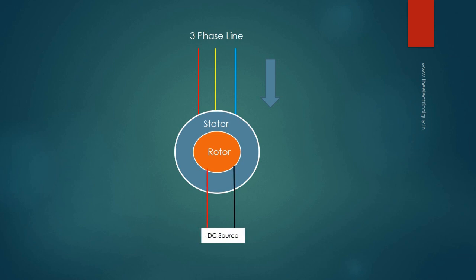If we excite the rotor with DC current, the rotor's MMF will help produce part of the required flux and less reactive power will be drawn. If we raise the excitation of the rotor further, it will produce all the required flux by itself and no reactive power will be drawn from the three-phase line — meaning the power factor of the motor is unity. If we overexcite the rotor, the stator will actually start delivering reactive power, and the motor behaves like a source of reactive power, just as if it were a capacitor.